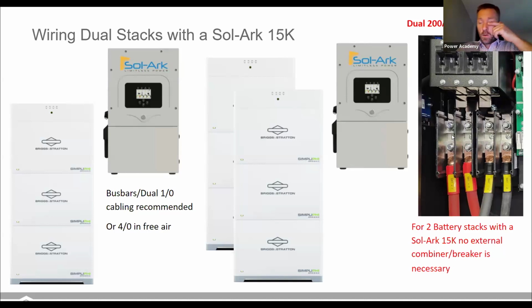Also, nice to point out that on a Sol-Ark 15K, you've got dual battery inputs. So if you have 2 stacks, you can run each of those stacks directly into the 2 battery input ports on the Sol-Ark 15K. You can use 2 sets of 2-aught cabling that way. For a single stack, we still recommend using dual sets of battery cables. Dual sets of 1-aught is fine. Or if you're not putting the battery cables in conduit, then a single set of 4-aught would be fine. And Briggs & Stratton does make a combiner if you want to combine those battery inputs on the Sol-Ark 15K.